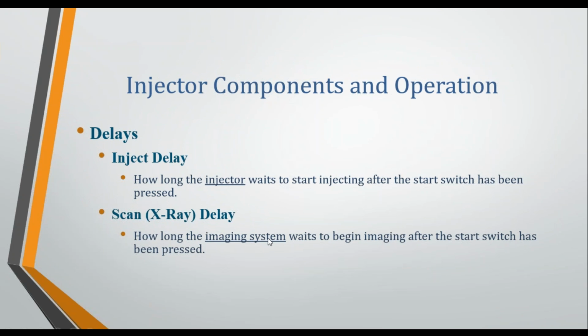All right. One of the other aspects that the operator can select on the display is something called a delay. We don't always necessarily want the injector and the imaging system to start at the same time. There are instances where we want the imaging system to start imaging, and then so many seconds later the injector starts injecting. That's referred to as inject delay. And obviously the opposite of that would be we want the injector to start injecting, and so many seconds later we want the imaging system to start imaging. That's referred to as scan or X-ray delay. There's 3 different types of contrast injectors. CT and MRI injectors refer to it as scan delay. Our angiographic or X-ray injectors refer to it as X-ray delay, but it's exactly the same concept.